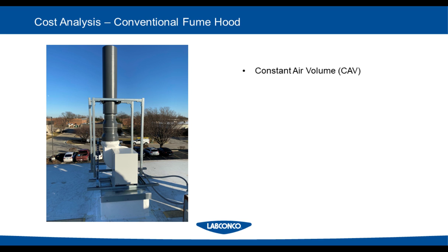So now I wanted to go over a cost analysis of different types of fume hood configurations that will allow you to decide what is best for my lab. The first one I want to talk about is a conventional fume hood, or a constant air volume situation. This is a scenario where the quantity of the exhaust air never changes, hence the name constant air volume. No matter where the sash is or the components inside the hood, you're always exhausting the same amount of air.